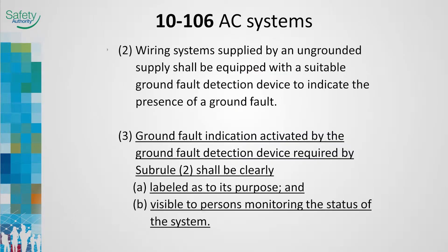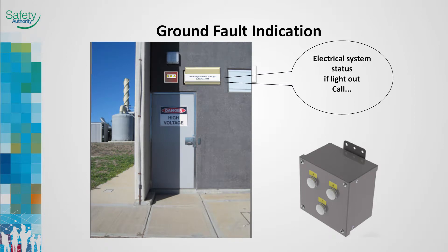Rule 10-106 AC systems. Sub-rule 3 was an Appendix B note in the 2012 Code Edition. The note was moved to Section 10, making compliance a mandatory requirement. Acceptable locations should be determined based on the type of occupancy or use and where those responsible for monitoring the status of the system will normally be situated. It is important that the location of the system's status monitoring equipment be located where the person responsible will receive the notification, and that the responsible person understands the situation and the consequences of ignoring the warning signal.